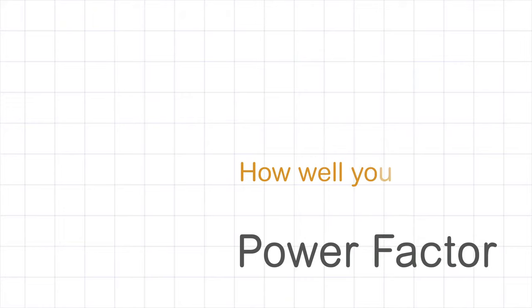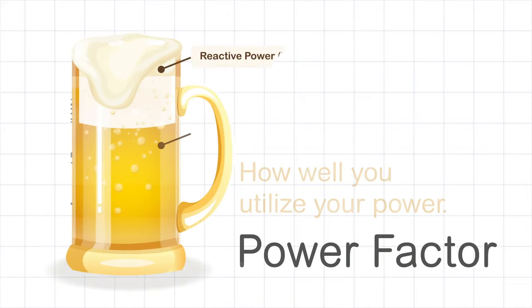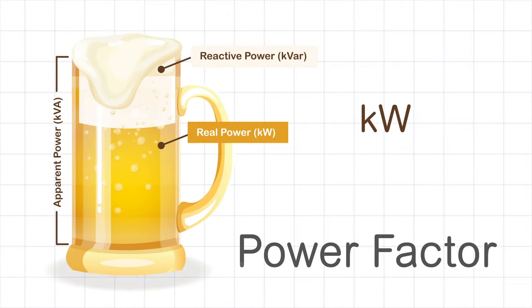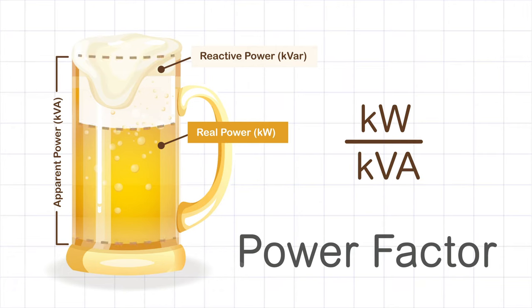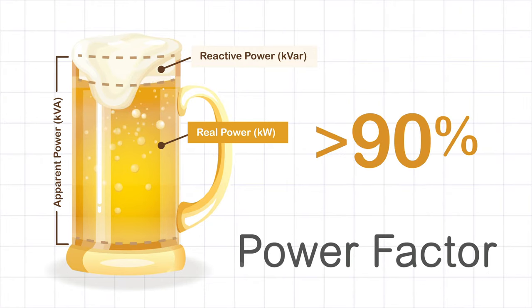Power factor determines how well you utilize your power. It's the simple ratio of your real power over your apparent power. The general engineering practice or rule of thumb is to keep the power factor in an electrical installation above 90%. Why correct power factor?